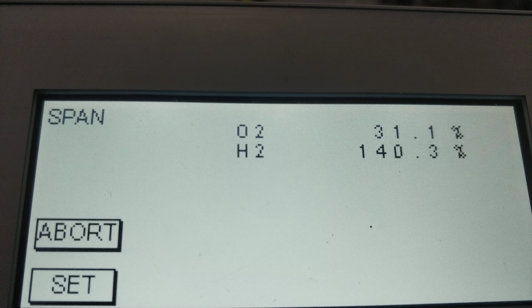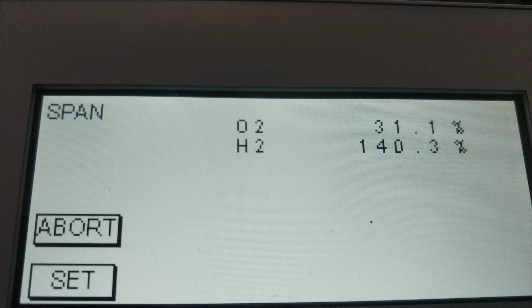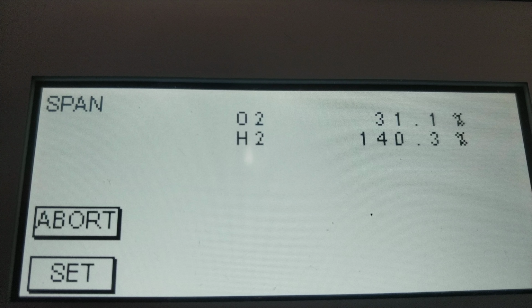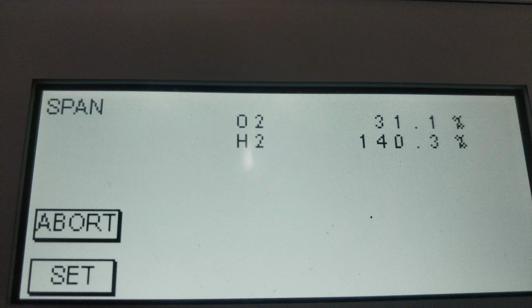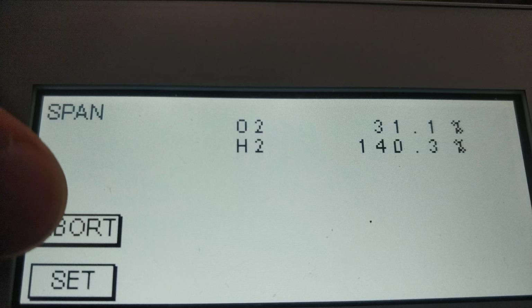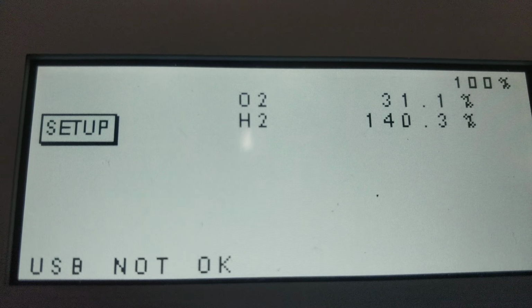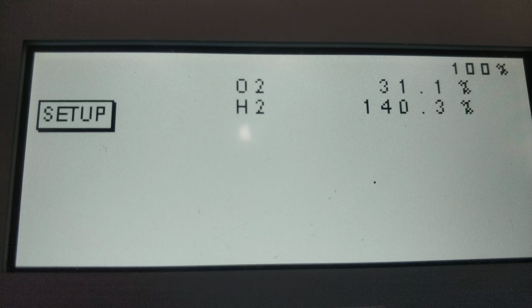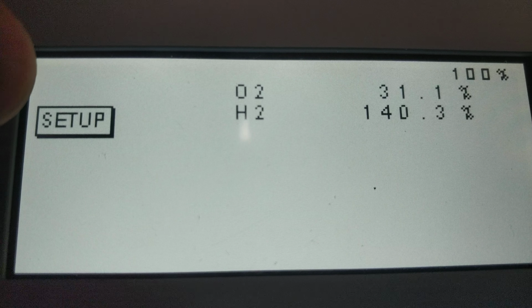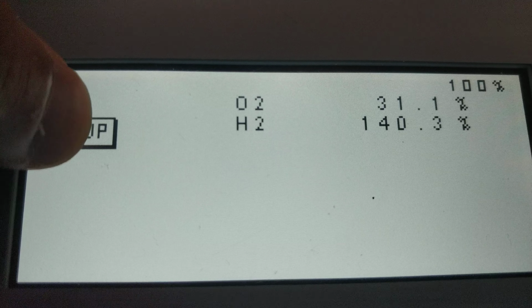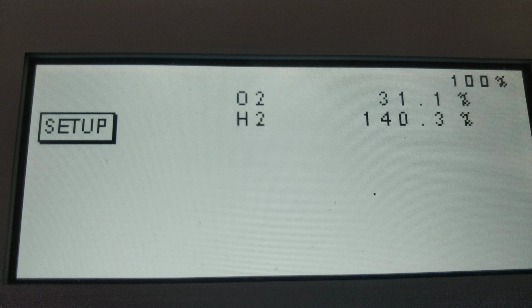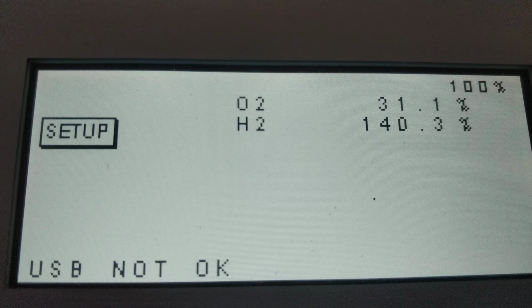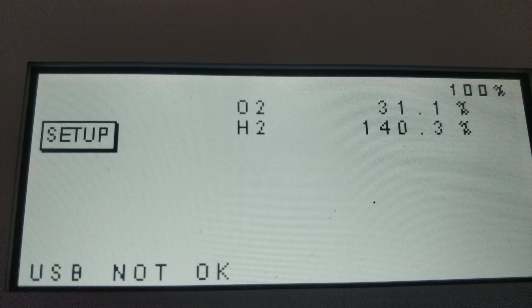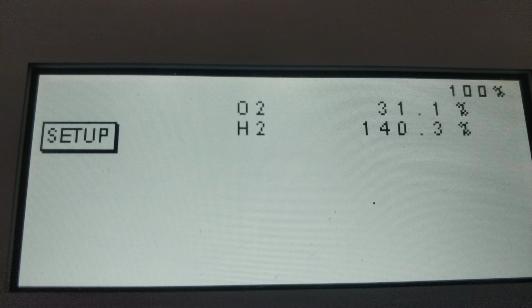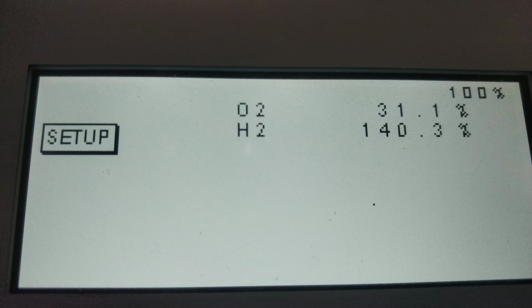So calibration, same thing. You would go to span. You would let your span gas go in through the analyzer at this point, and once the readings are relatively settled, press set, and then you should be good to go. I'm going to press abort. Now, once we've done the calibration, one more thing that we do want to do is ensure that the CalCheck is re-enabled. We just got to wait a couple of seconds because I pressed abort here. But it's always a good idea to have the CalCheck enabled. It acts like a form of insurance against erroneous calibration values.